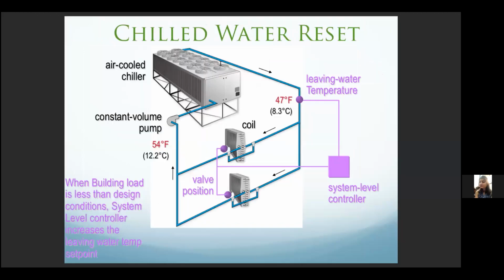Chilled water reset is another optimization strategy where, if the load of the building is less than designed, the system level controller can understand the parameters in the building and say, okay, we don't need to run the chiller as hard as we would need to on design, so we'll just increase the leaving water temperature and still be able to satisfy the space, hence saving energy.